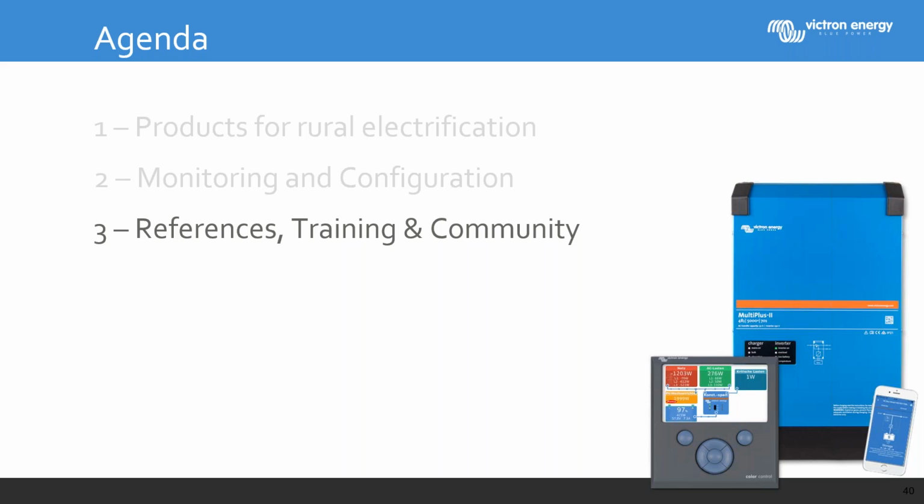It's difficult sometimes to have one MultiPlus with an external changeover switch working with a grid and then switching over to work with a generator. There are different settings required, and that can be challenging sometimes. And sometimes it means that generator is just not compatible. But we have lots more information to share with you regarding that, so please make contact with us.